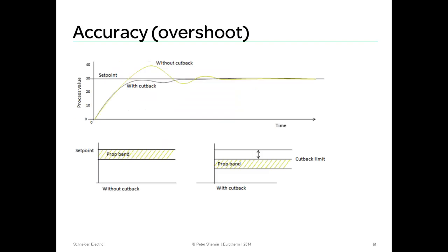One of the primary issues in running a TUS is minimizing any overshoot in the control sensor. A properly mapped furnace with multiple TUS sensors in the extremities of the work zone will magnify a 1 degree overshoot in the control thermocouple by 5 or 10 times across the TUS sensors. This is for certain furnace setups. Using overshoot inhibition features available on higher accuracy instruments - named Cutback for Eurotherm controllers - helps with avoiding this overshoot. This is the secret sauce in Eurotherm control and other instruments. When I first used Eurotherms as a customer over 15 years ago, I benefited from these features without even realizing what was helping me with my control accuracy.